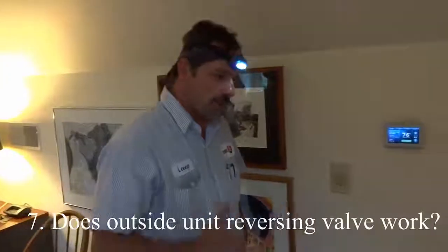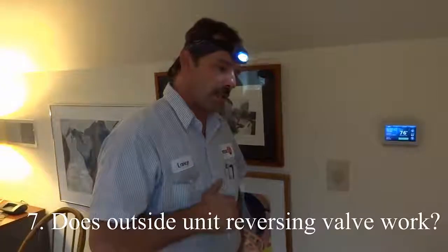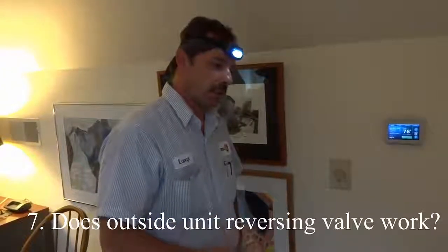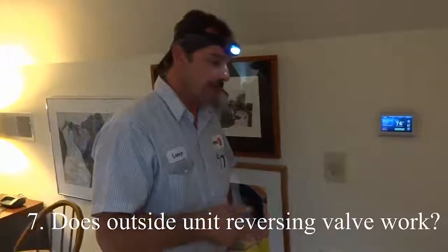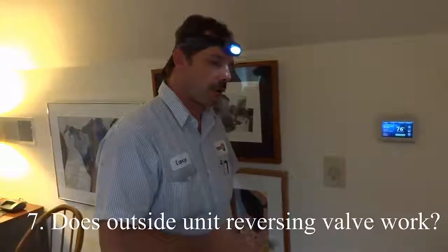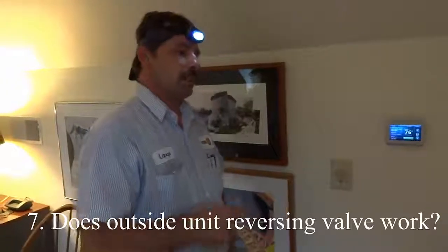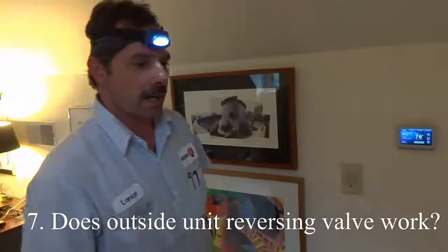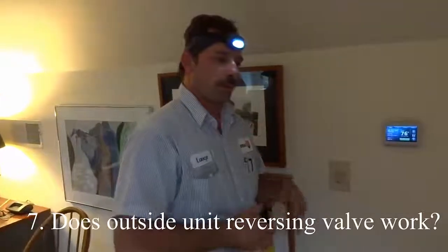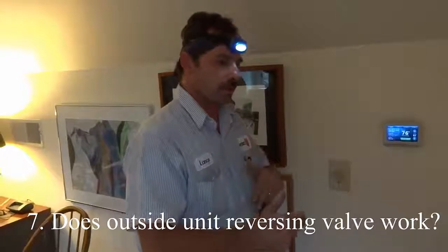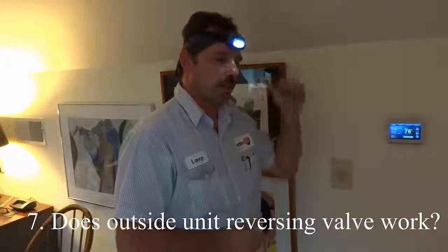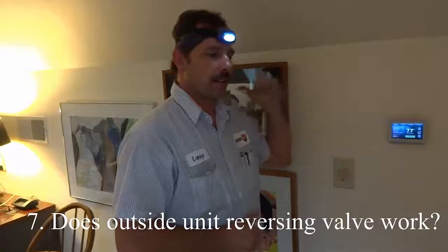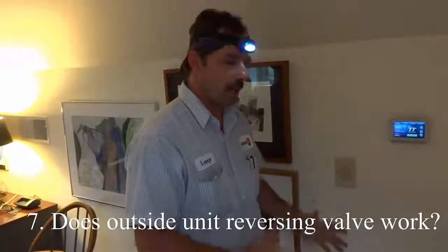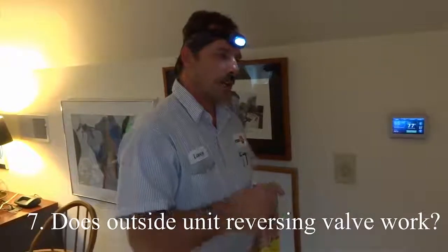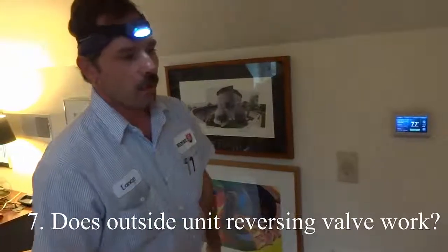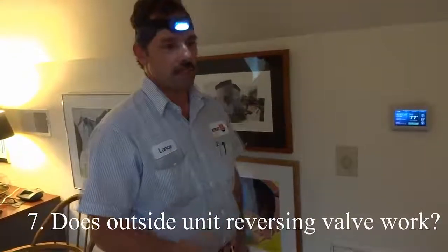Number 7, he verifies that the outside unit reversing valve works in defrost mode. The outdoor coil freezes up in heat mode, and there is a sensor on the line that will indicate when it needs to thaw the coil. It has a timer or a demand control board that will switch the reversing valve, turn the heaters on, and turn off the outdoor condensing fan. This traps the heat and melts the ice off the coil. When the sensor senses that the coil is approximately 50 to 55 degrees, it will kick in automatically back to your regular heat cycle.